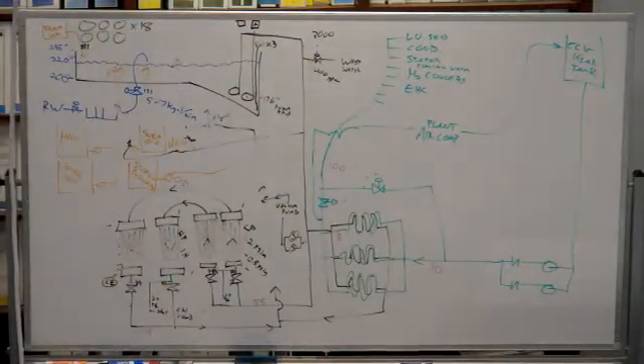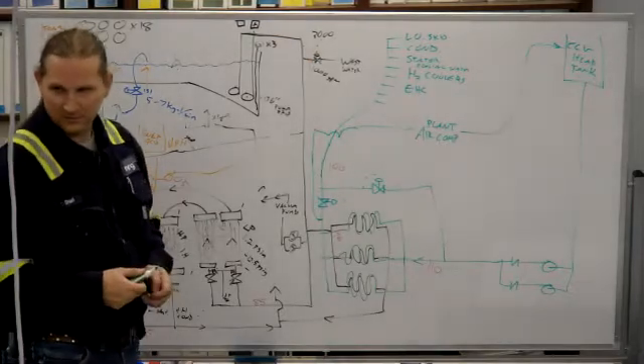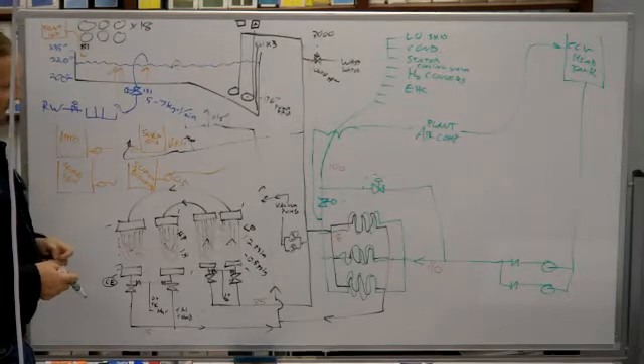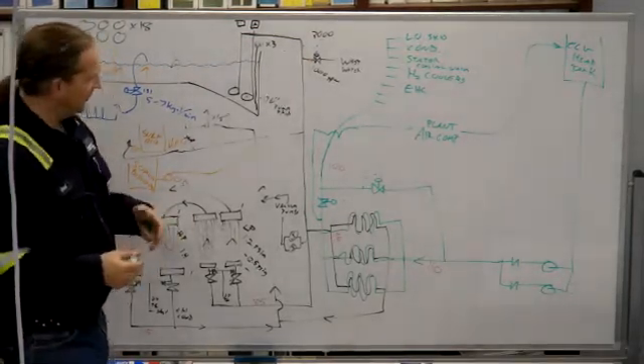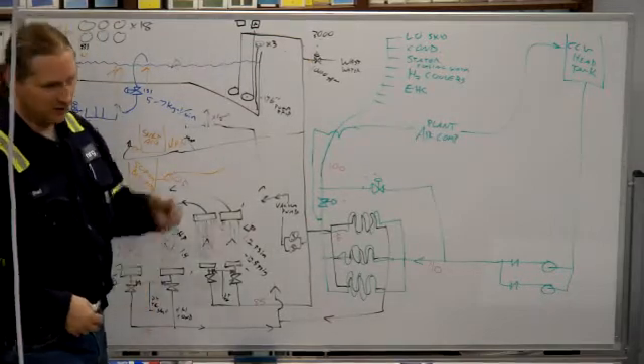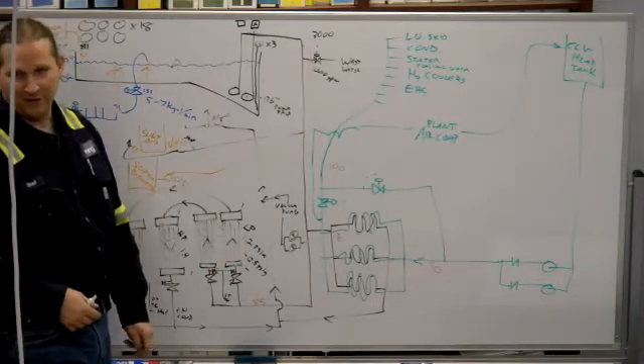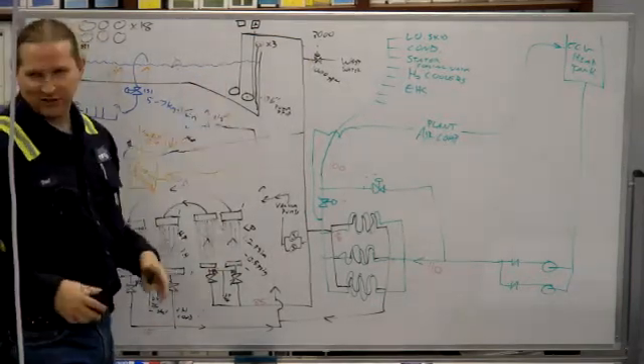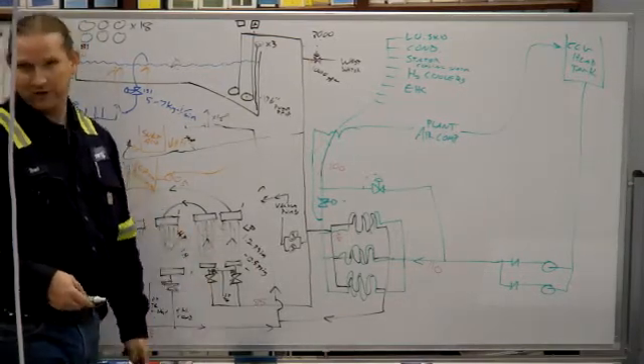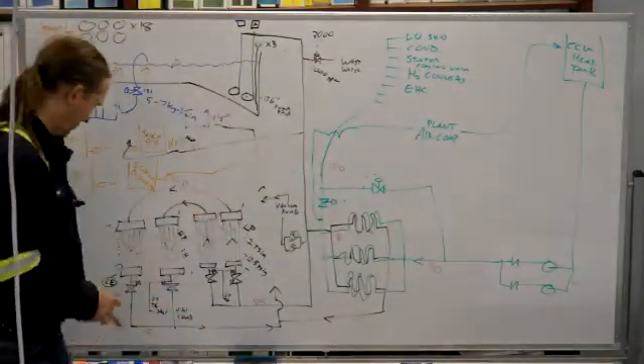Is that what we use on the fans in the switch yard? Alright, so the generator's step-up transformer in the summer has trouble maintaining its temperature below 95. There are sprinkler heads that blow onto the heat exchangers and those are coming off of potable water, because potable water is cheaper. This is high quality water. It's coming off the demin.